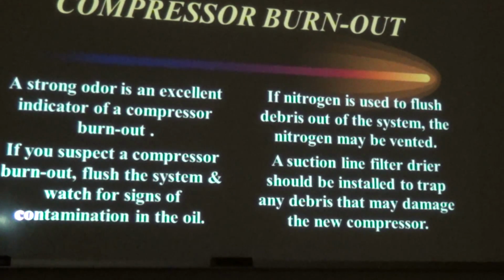This slide appears in all of the type 1, type 2, type 3. A strong odor is an indicator of compressor burnout. If you think that your compressor has burned out, flush the system and watch for signs of contamination in oil. If nitrogen is used to flush the debris out of the system, nitrogen can be vented to the atmosphere. A suction line filter dryer should also be installed to trap any debris following the repair with the new compressor.